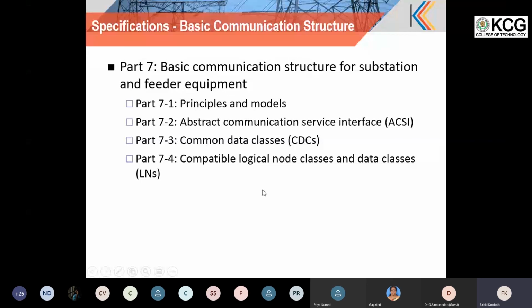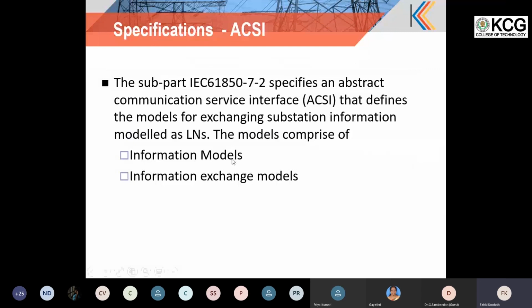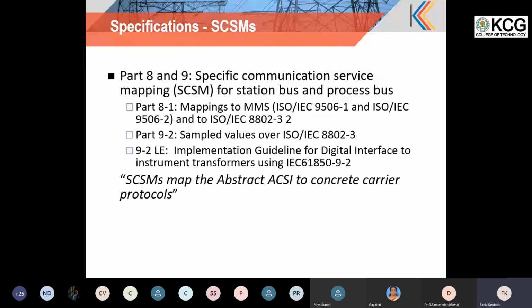And 7-2 details about the information model. Information models are nothing but the logical nodes and their data elements. Then the information exchange model is how to exchange the data, that is report, GOOSE, sampled value. All these details are given in the 7-2 document. 8 and 9 specify the communication service mapping to MMS, GOOSE and sampled value. So this is an elaborate standard.